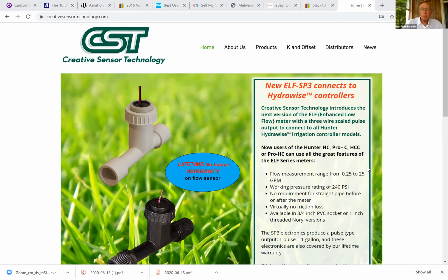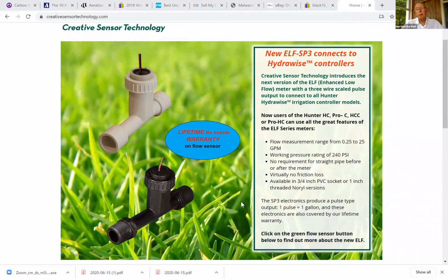Okay, glad to join you, Chris, and yeah, let's try and straighten out a couple of pieces of information, or maybe not that, but just the confusion a little bit. We've got the website screen up here to show you that we have this new product called the ELF, and ELF is not the guy out of the Keebler cracker ads, but it's actually a shortened version of calling it an enhanced low flow sensor. When we built and developed this, we were shooting for something that would measure down to low flows that are good for the drip requirements that are coming out now. As many of you know, we've got zone valves now that will go down to 0.2 gallons per minute and operate. So we said, let's shoot for a flow sensor that'll get down to low flows like that. So we developed the ELF, and basically it came out on the market in 2019.